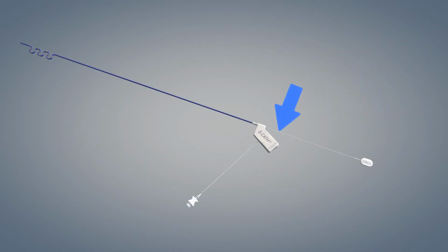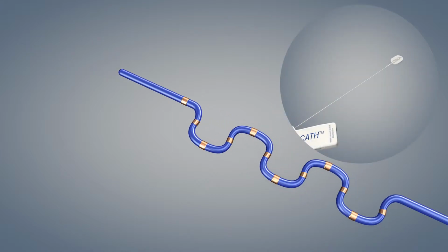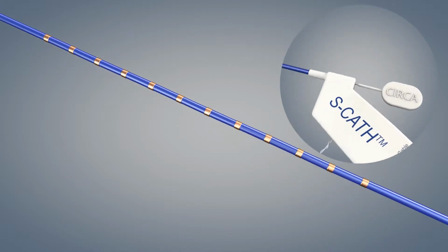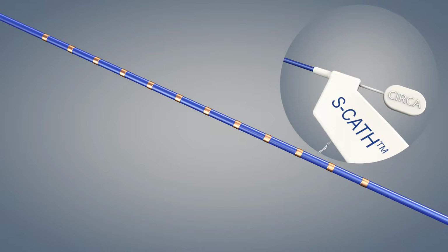Hold the stylet close to the connector housing and allow the probe to hang vertically. Advance the stylet completely until the white end of the stylet reaches the connector housing. Apply a water-soluble lubricant to the outside of the probe and insert the S-Cath immediately into the esophagus. The probe may be inserted either orally or nasally.